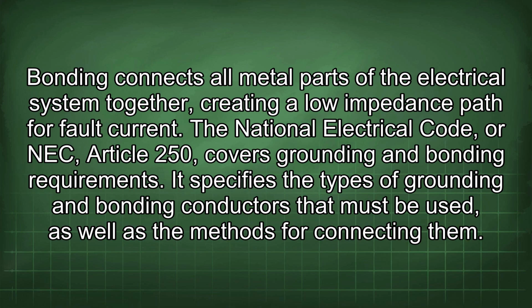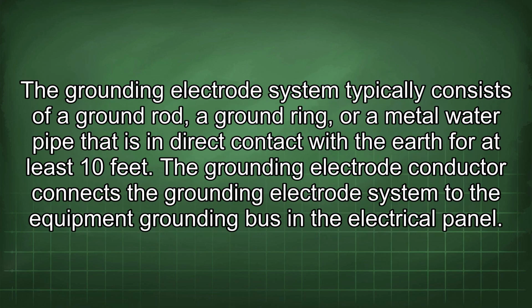The National Electrical Code, or NEC, Article 250, covers grounding and bonding requirements. It specifies the types of grounding and bonding conductors that must be used, as well as the methods for connecting them. The grounding electrode system typically consists of a ground rod, a ground ring, or a metal water pipe that is in direct contact with the earth for at least 10 feet.